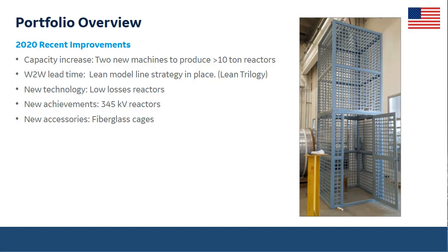Traditionally, high voltage, extra high voltage reactors, shunt reactors, were oil filled, iron core, the first one that I showed on the slides before. Now they've been replaced more and more. That's a new trend to have them made of dry type air core design. So we have reached the 345 kV level. And this is just an example of some innovation that we're doing.